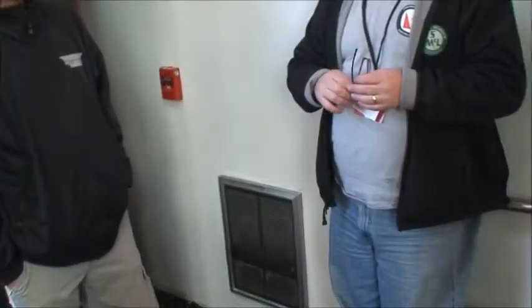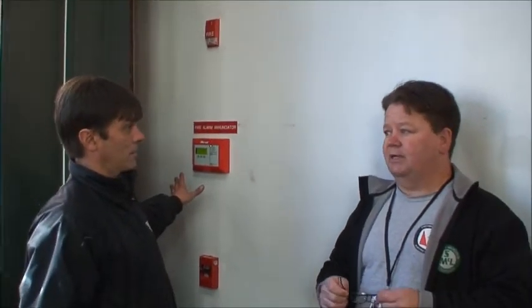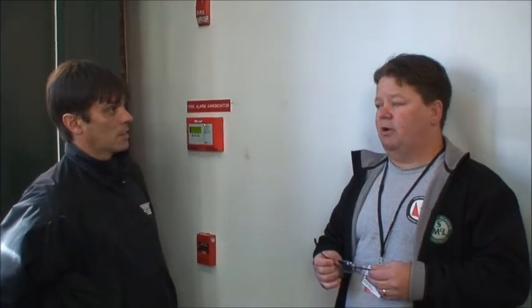They call them local smoke detectors, just like the ones in your home. They have local alarms, sounder bases that go off, and in the handicap units they also indicate with a strobe. So billowing smoke into the hallway will set the alarm off, and then these doors will unlock. Billowing smoke in the apartment will not set this off. It has to reach a hallway smoke detector.